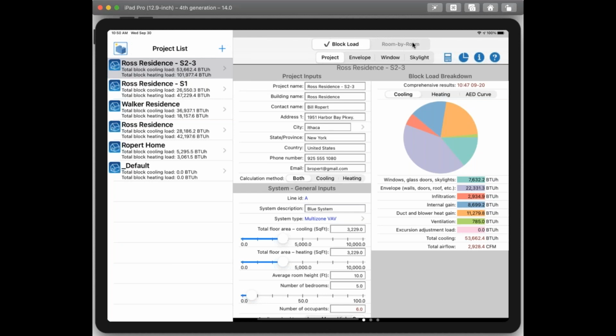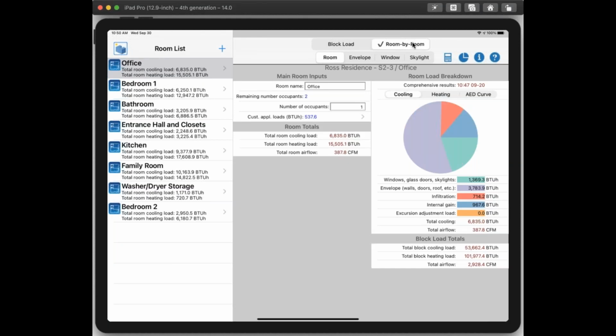But you can take it one step further and do a room by room analysis. We're getting more granular here, because now we want to see what the cooling and heating loads are for each room. Maybe even more importantly, we want to determine the airflows for each room, because if this is a retrofit or new construction, we want to know what size ductwork to run into each room. Based on the airflow values, we can determine the duct size. So this is important for more granular analysis of the home.